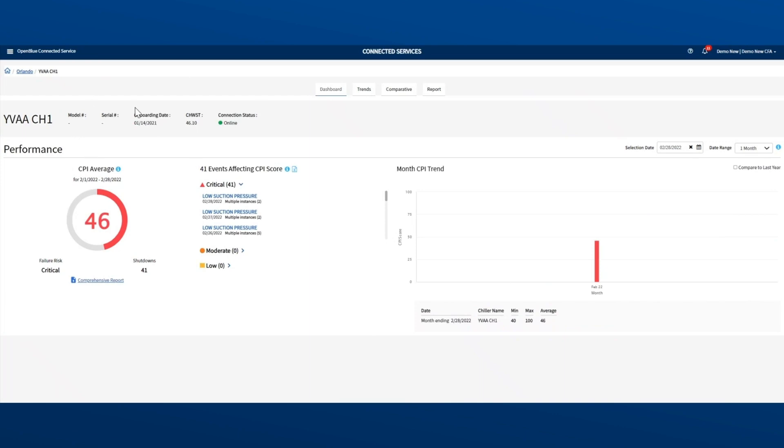Now you are reviewing that unit in greater detail. On the top left, you can see the chiller's model number, serial number, and connection status. Straight away, you can see this unit has scored just 46 out of 100 in the last month, and there have been 41 shutdown events.